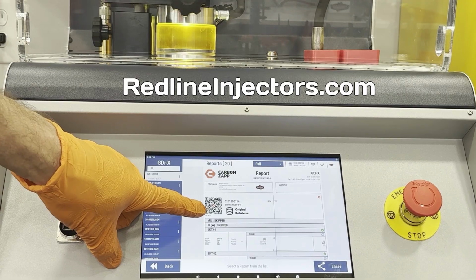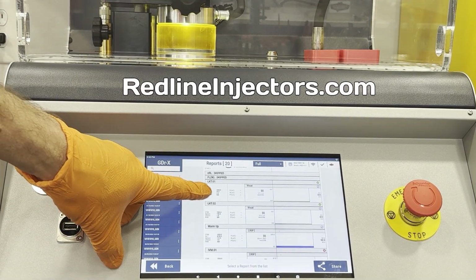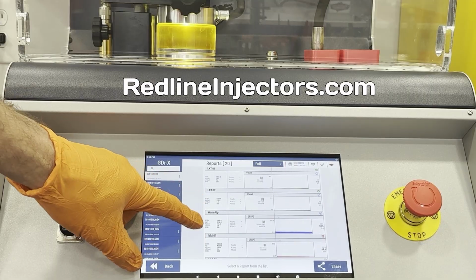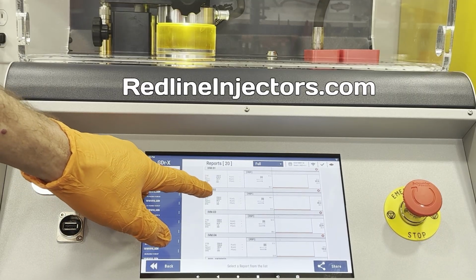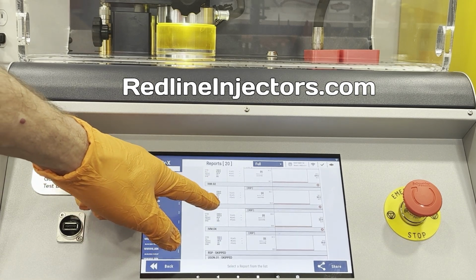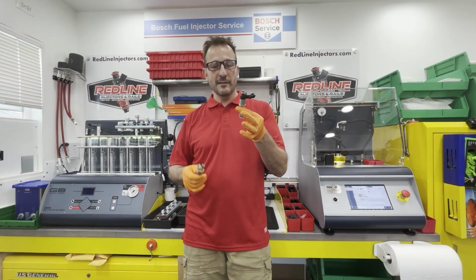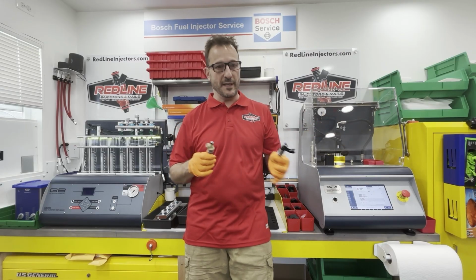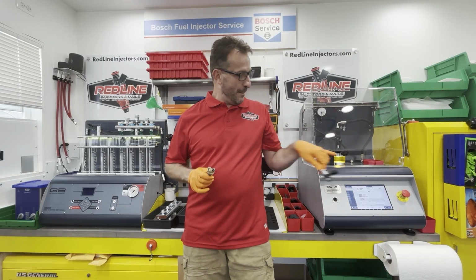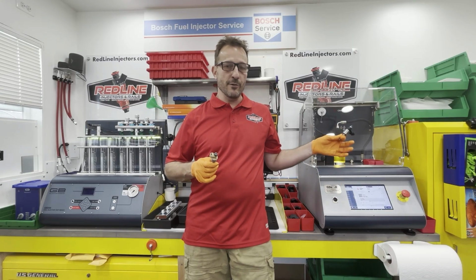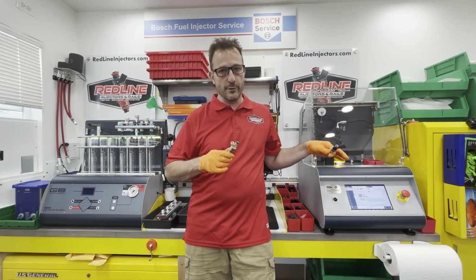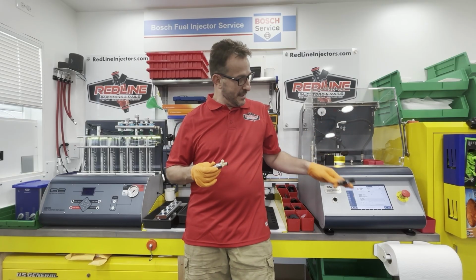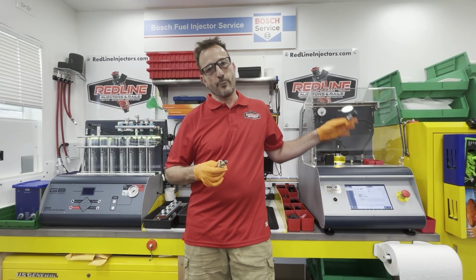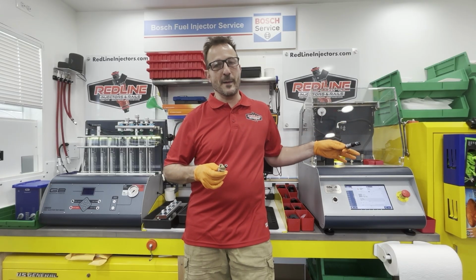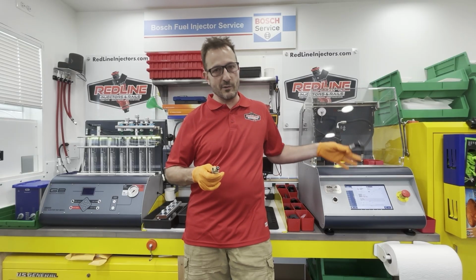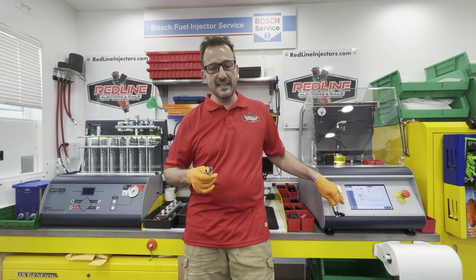So there we go. And you can see the leak tests were green. The warm-up passed, but the 4 performance tests all failed with red. There we have it. GDI, MPI, the injector's still in the machine, but anything meaningful happens inside the machine. There's no spray pattern, there's no human eyeball calibration, there's no measuring fluid in a vial. Everything's done internally in the machine based off pressure, velocity, and volume that's expected of fluid being injected into extremely precise sensors. So anything happens inside the machine.